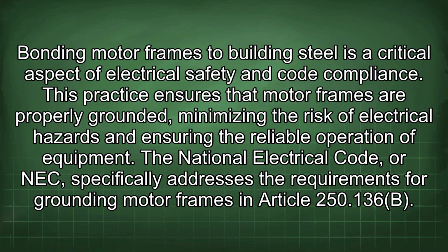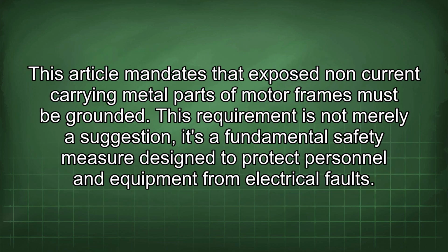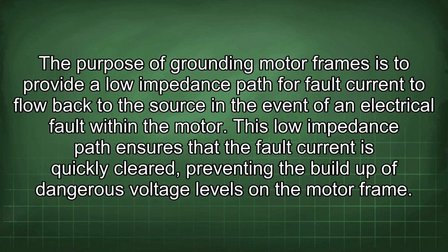of equipment. The National Electrical Code, or NEC, specifically addresses the requirements for grounding motor frames in Article 250.136(B). This article mandates that exposed non-current carrying metal parts of motor frames must be grounded. This requirement is not merely a suggestion, it's a fundamental safety measure designed to protect personnel and equipment from electrical faults. The purpose of grounding motor frames is to provide a low-impedance path for fault current to flow back to the source in the event of an electrical fault within the motor.